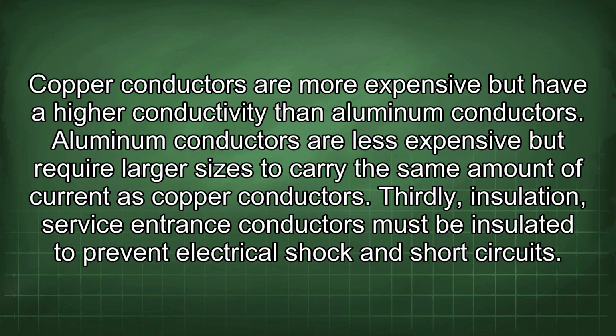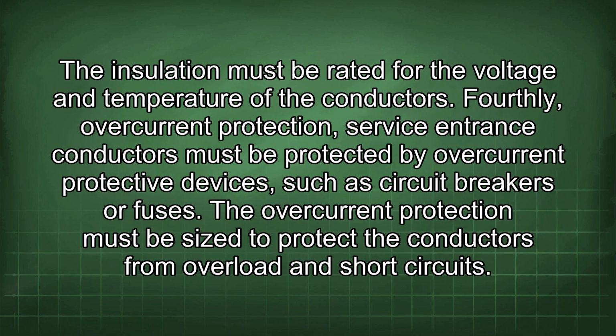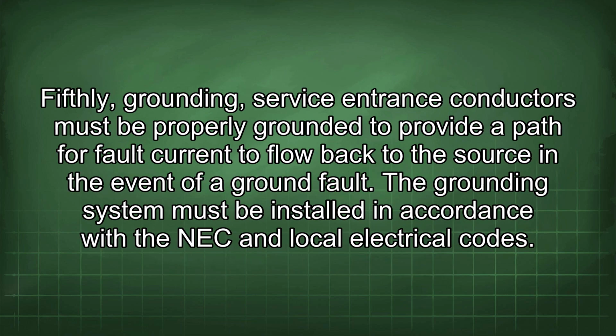Thirdly, insulation. Service entrance conductors must be insulated to prevent electrical shock and short circuits. The insulation must be rated for the voltage and temperature of the conductors. Fourthly, overcurrent protection. Service entrance conductors must be protected by overcurrent protective devices, such as circuit breakers or fuses. The overcurrent protection must be sized to protect the conductors from overload and short circuits. Fifthly, grounding. Service entrance conductors must be properly grounded to provide a path for fault current to flow back to the source in the event of a ground fault. The grounding system must be installed in accordance with the NEC and local electrical codes.